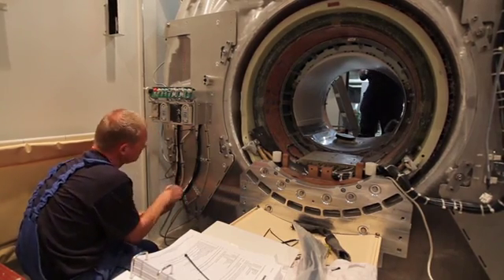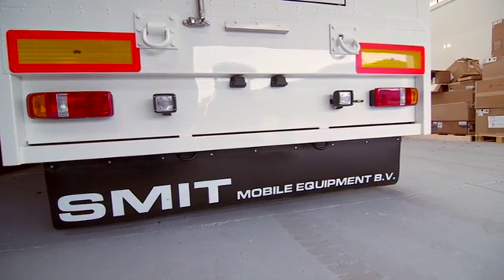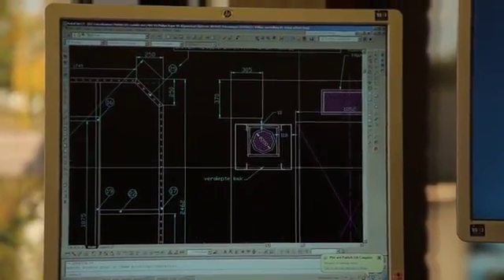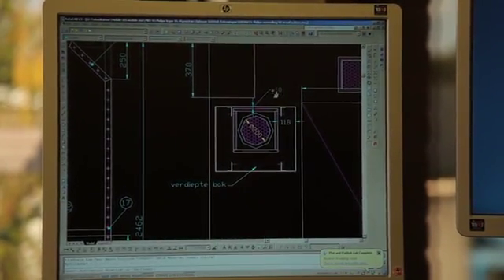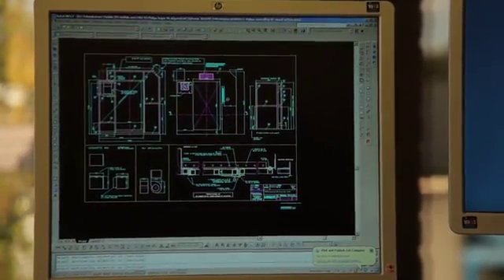There are some specific options on these units to make sure they can withstand the circumstances in the field. For example, the air conditioning chiller system is an upgraded system. There are special reinforcements to make sure that the units can be tied down in an airplane, which is not standard for us because most of our units go over the road or by ship. The manufacturing is similar, but the whole logistic project behind it — including all the supporting elements like the UPS system and the special support generators — that's special.